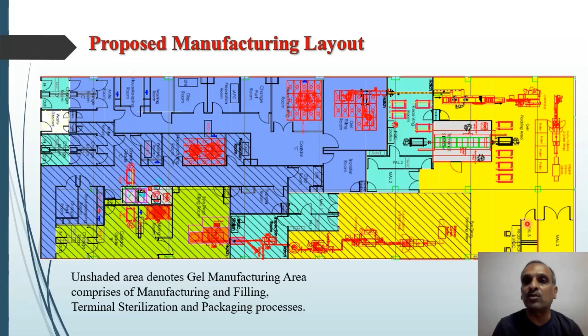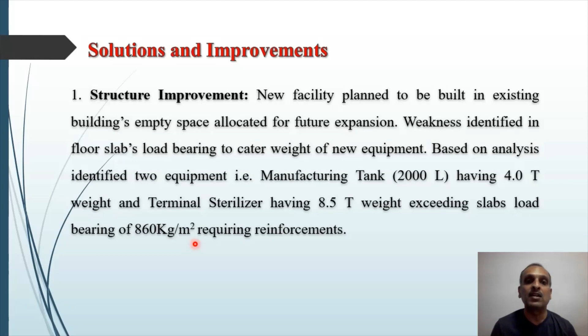The new facility is planned to be built in existing buildings, with empty space allocated for future expansion. A weakness identified is in the slab's load bearing capability to cater to the weight of the new 2000 liter manufacturing tank, having 4 ton weight, and the terminal sterilizer having 8.5 ton weight, which exceeds the slab's load bearing capability of 860 kg per meter square, requiring reinforcements.